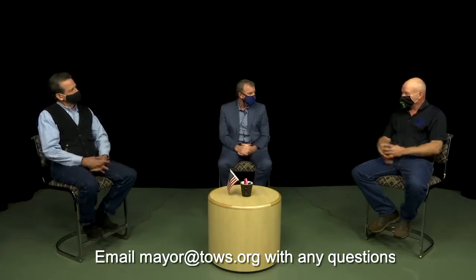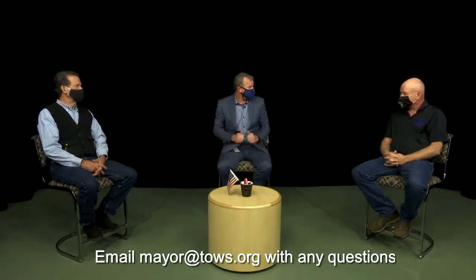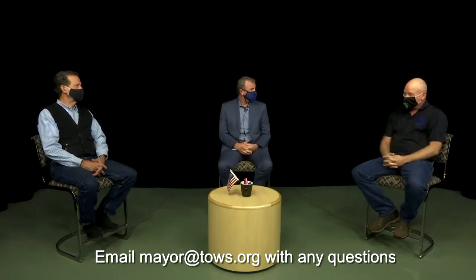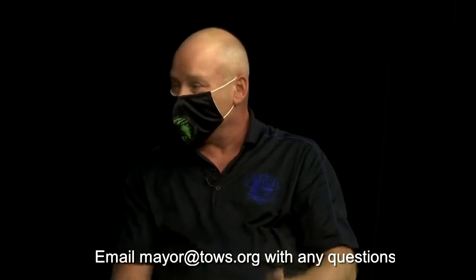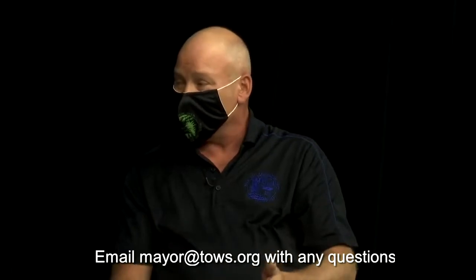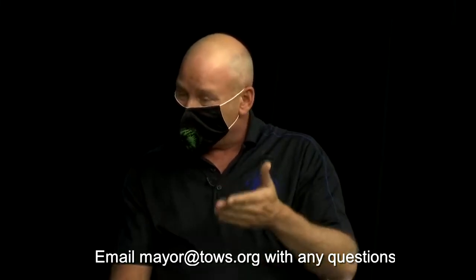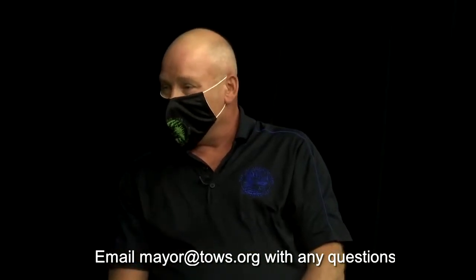Scott, I know you've been doing some work around the buildings since March 13th. Our guys are out there working on the buildings in terms of bringing in that fresh air. Can you talk about the work that's been happening? Sure. We've been going through, school by school. It is important to bring in fresh air, and it's important to know that we have that capability in every school. We also have the capability of controlling that fresh air intake — we can increase or decrease it as needed. If CO2 levels are a little bit high, the dampers open automatically and start bringing in more fresh air, which only adds to our air exchange rate per hour.